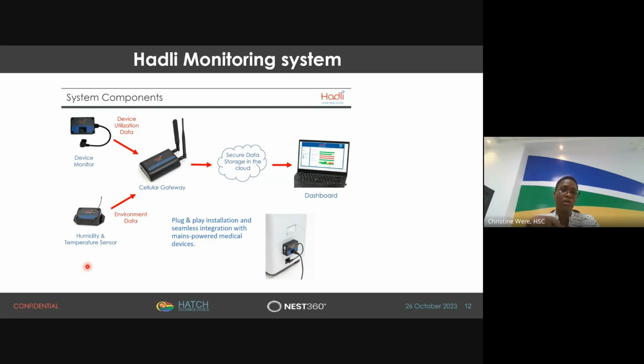These two sensors connect to a cellular gateway through radio communication, so they need to be in a specified environment, like within a certain circumference, since there's a limited distance at which they can communicate. Mostly in a room you'll have one gateway and several sensors. The good thing is that the radio signal can even be sent beyond a wall, so even if your newborn unit has different compartments, the signal will still reach the router as long as it's within the specified distance.